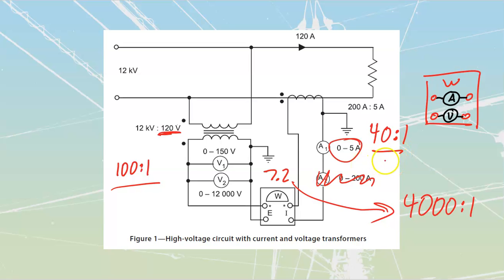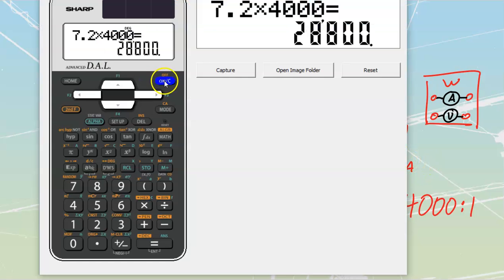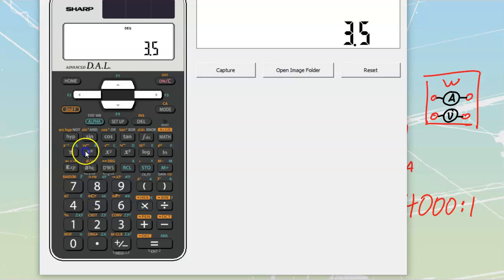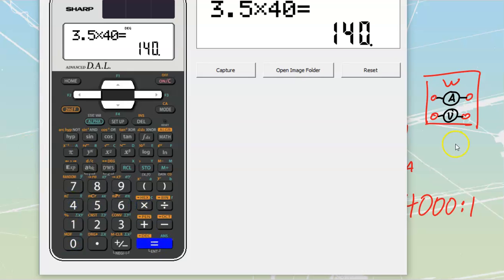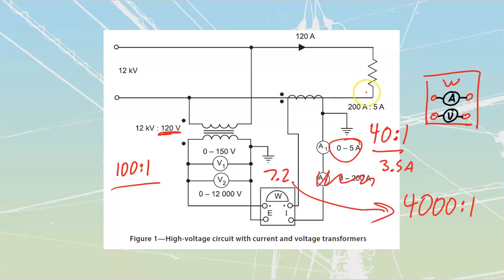But they want you to learn about these multipliers. If this was coming in at 3.5 amps, I would take that 3.5 amps, multiply it by 40, and that would tell me that the actual true current traveling through that circuit would be 140. I should be able to read that off of this one directly, but it's a way for you to verify. We'll go on to the very last one over here, which is going to be my voltmeter.